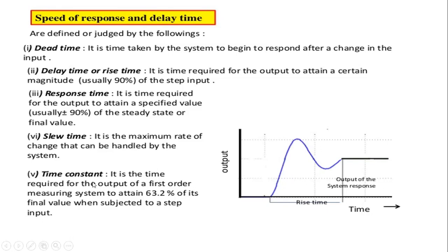The time constant is very important and will be studied further when covering order of systems. It is defined as the time required for the output of a first-order system to attain 63.2% of its final value when subjected to a step input. The instrument typically reaches steady state after two to five time constants. This is why you should always wait before taking a reading — to account for dynamic errors, dynamic lags, and the time constant needed to reach steady state.